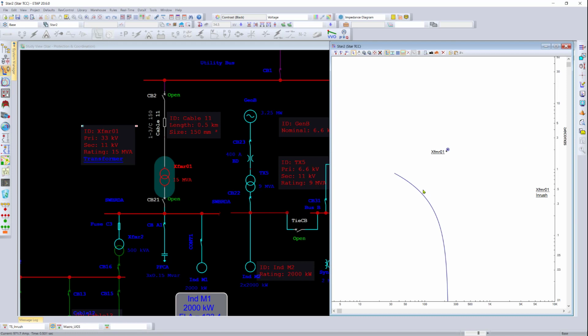If we go ahead and zoom in and look at the details of the inrush, we can turn on our settings and see that it's actually using 12.44 with the time constant in cycles. So therefore, the parameter estimation that calculates the inrush curve inside the transformer is available not only for transient stability, but also in ETAP Star, now in ETAP 20.6.